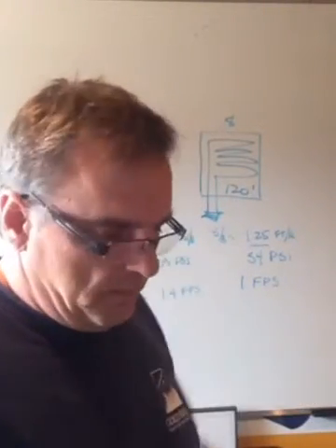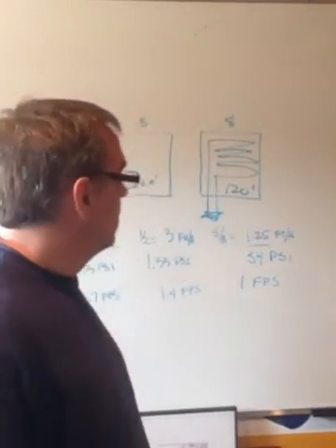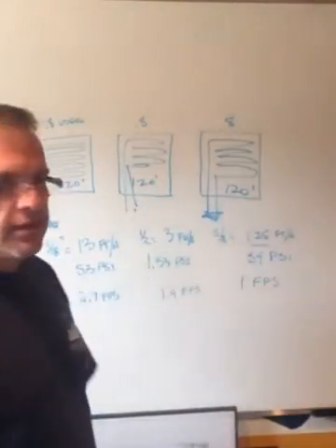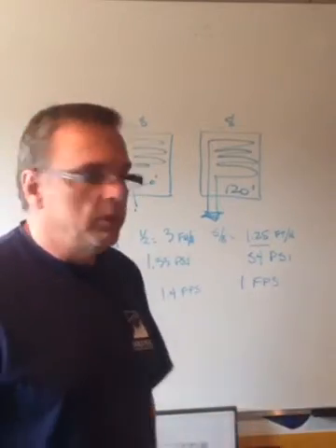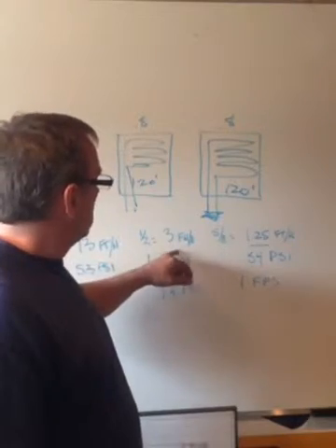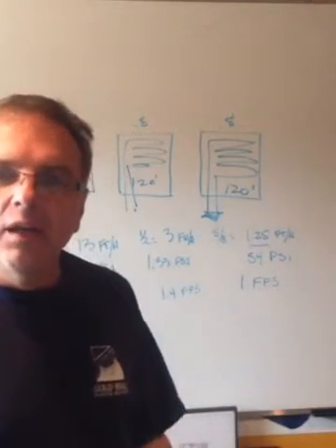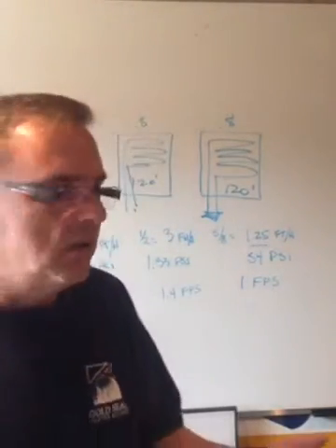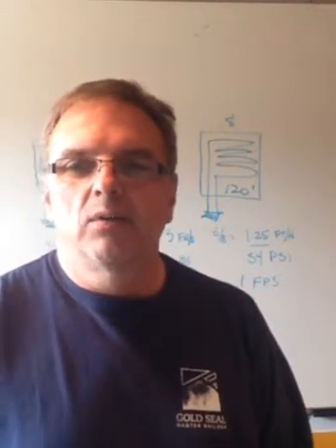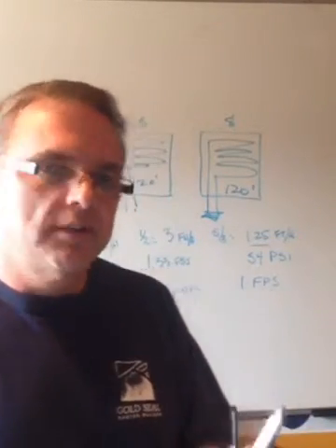very shortly they developed a smaller diameter tubing, 1/2-inch tubing, same pipe of course, but laid out in the same manner. Tubing's the same length, but it's just a smaller diameter, in this case 1/2 inch. I do the math on that, I find out there's 3 feet of head in that loop, or 1.5 PSI pressure drop, and you know, that's still a little bit low. I mean, in this case I'm only moving at a 1.5 foot per second rate, and that's still a little slow to get the air out of the system, but that is typically what every designer will use today.